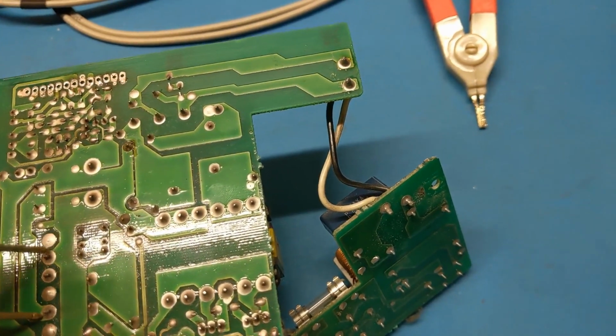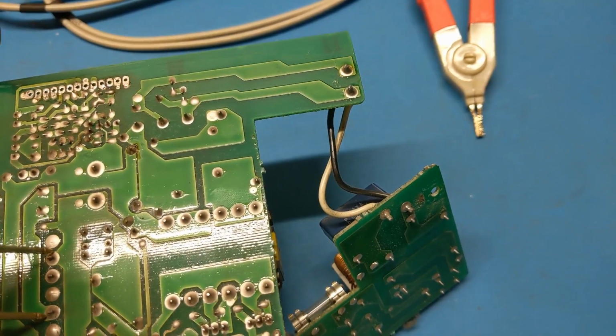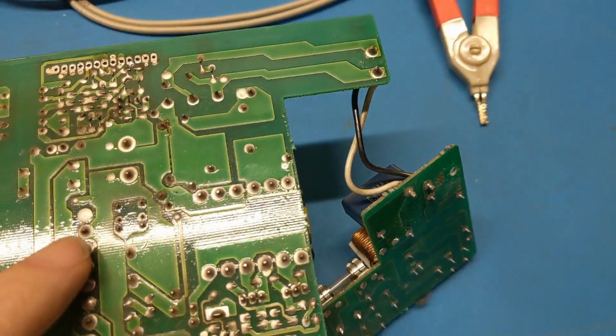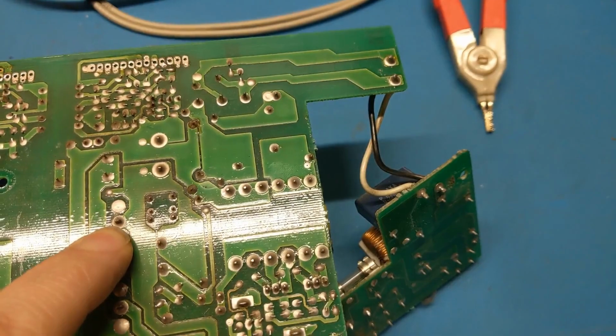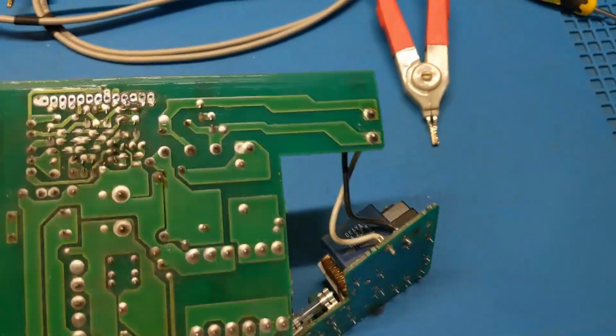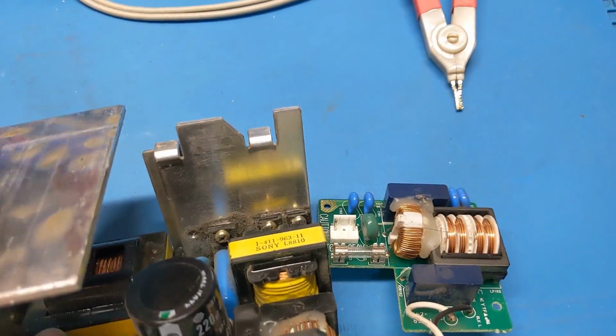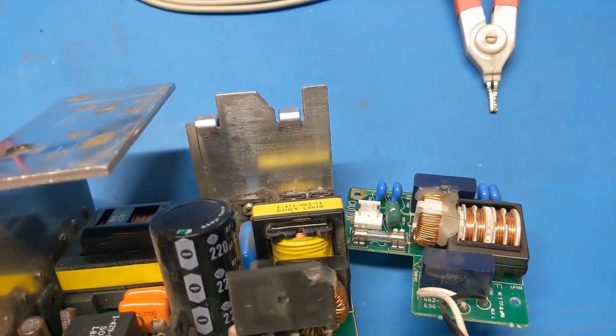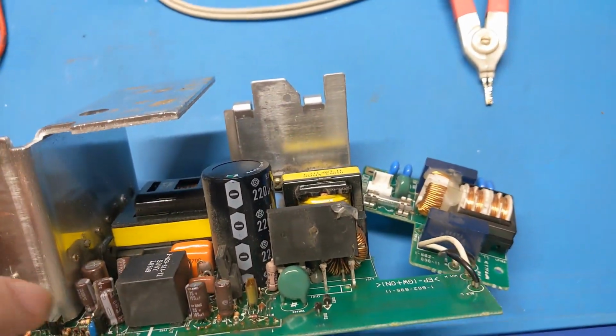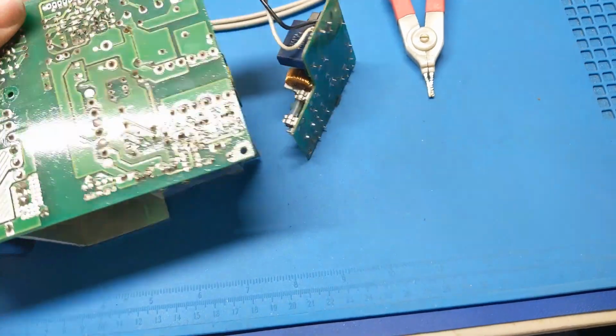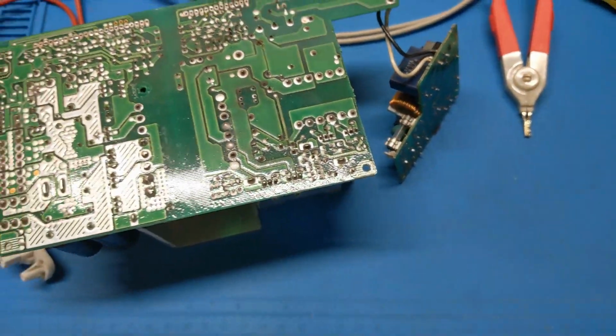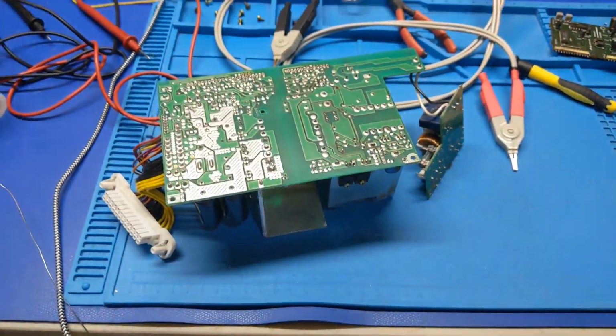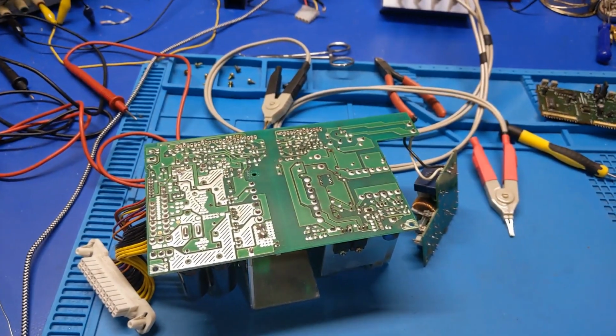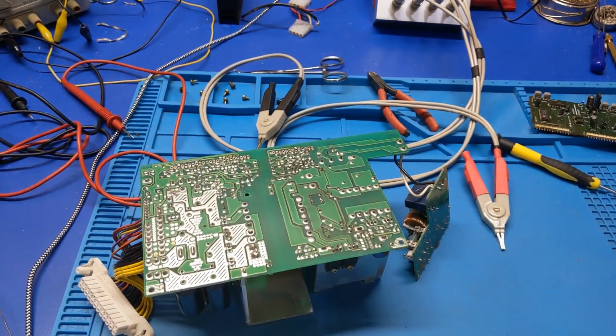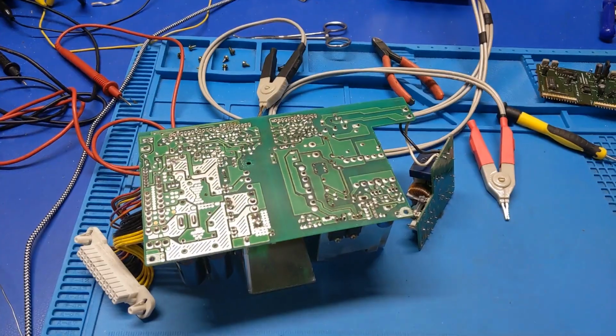From here, it's open. So I need to see if that is actually connected on this transformer, because I've never had this transformer out before. I need to pull this transformer and verify the winding, because if that's open, that's a full stop right there - that's why it's not working, and it'll never work again if that's open. So let's check that first before I go any further.